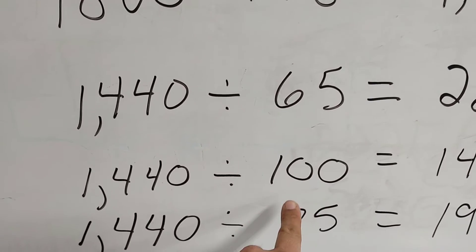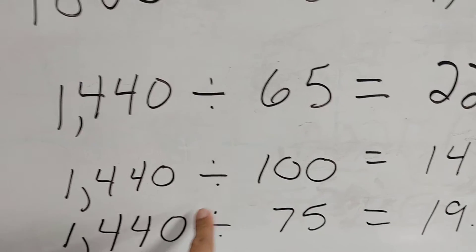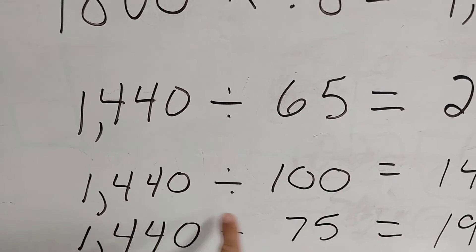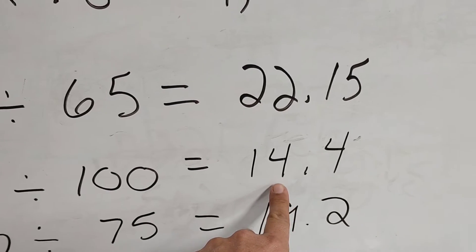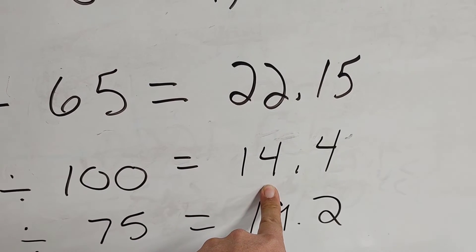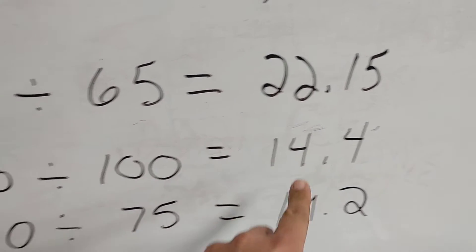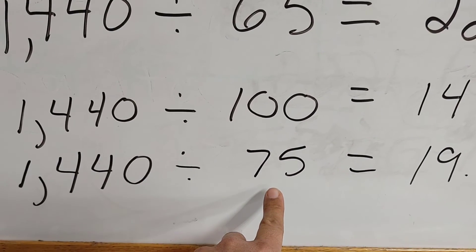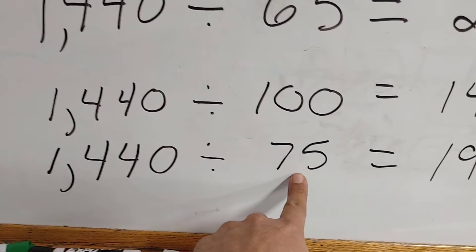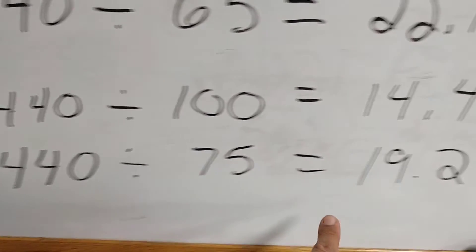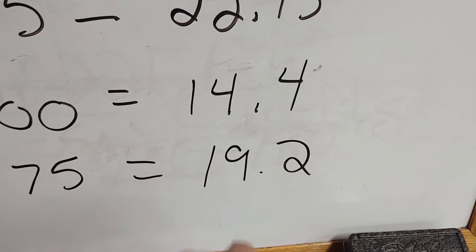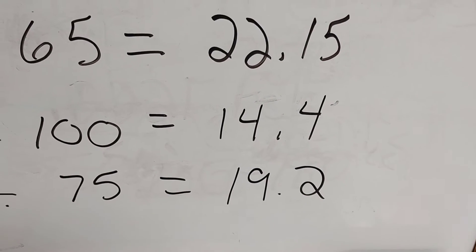And if you're using a 75 watt rated fixture, you're going to divide 1,440 by 75, and you're going to have 19 fixtures that you can put on that circuit. So using the example we just went over, you're going to be able to go with 22 fixtures for 65 watts, 14 fixtures for 100 watts, or 19 fixtures for 75 watts.